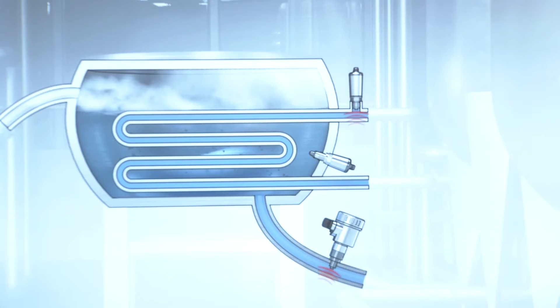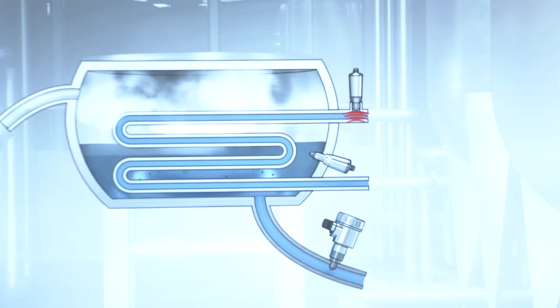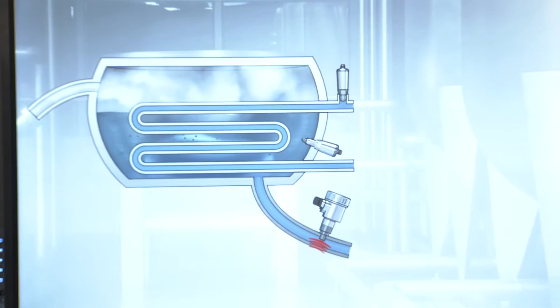When you have a look there, you have two types of sensors here. In the cooling line, we have the VEGABAR 28 with a low demand on the hygienic design, because it's only the cooling liquid inside, which cools it down very easily, and you have no direct contact to the media. The media here is water for injection, and the VEGABAR 82 is directly in contact with the water for injection. So this sensor has a high need to be robust and to be inert against the media. Therefore, we use the VEGABAR 82 with all the FDA approvals to make sure that nothing from the sensor goes into the water for injection, to keep the water for injection really clean.